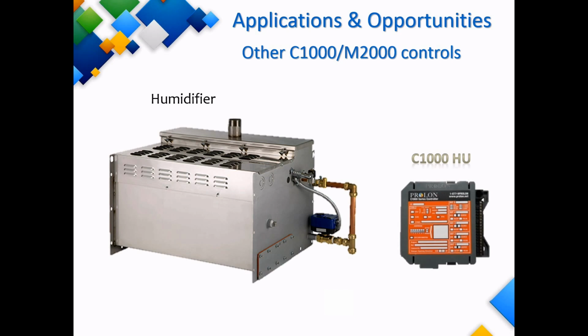Prolon has a humidity controller, the C1000HU. This device can control humidifiers, whether they are on-off or modulating. The controller has an outside reset scale and high limit. The controller can also be used for dehumidification purposes.